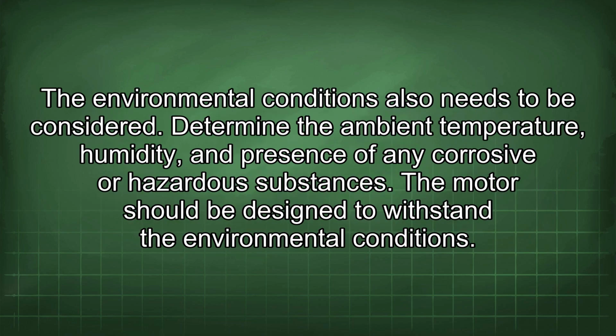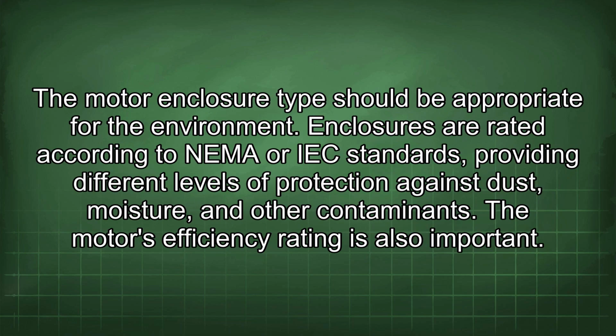The environmental conditions also need to be considered. Determine the ambient temperature, humidity, and presence of any corrosive or hazardous substances. The motor should be designed to withstand the environmental conditions. The motor enclosure type should be appropriate for the environment. Enclosures are rated according to NEMA or IEC standards, providing different levels of protection against dust, moisture, and other contaminants.